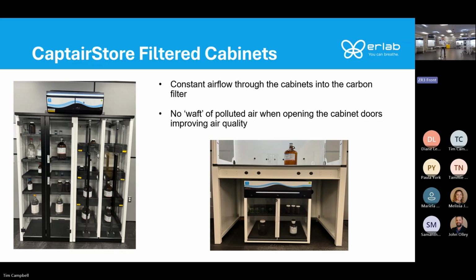A lot of times they're odorous. You have different samples. Where are you storing them? Probably on the counter in a closed cabinet with no ventilation. This adds carbon filtration to the cabinet. So all air is constantly pulled past all those samples, all those bottles. Chemical vapors are captured in the carbon filtration. Clean air is returned to the lab space.